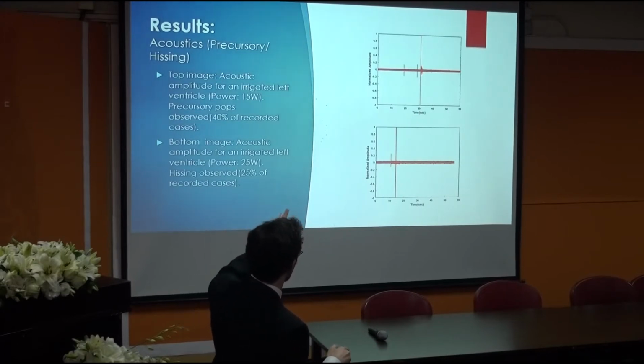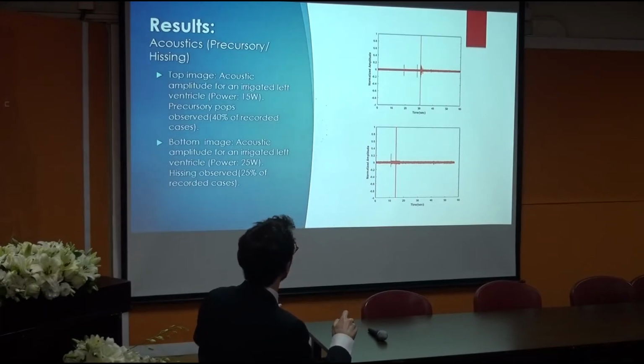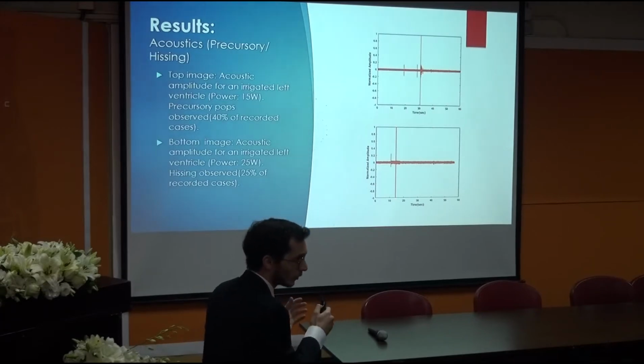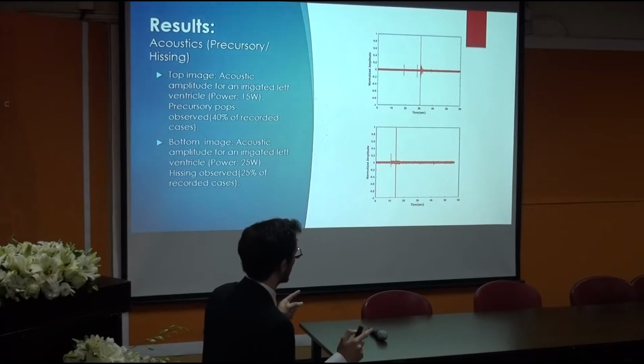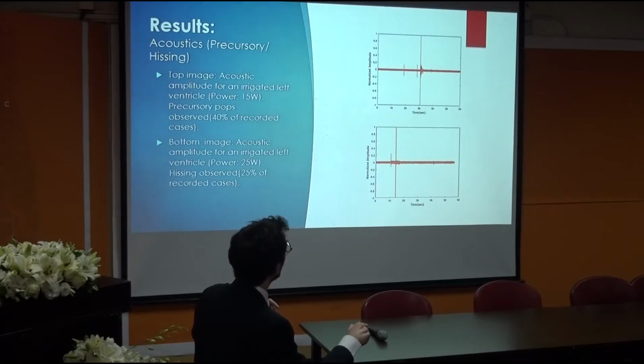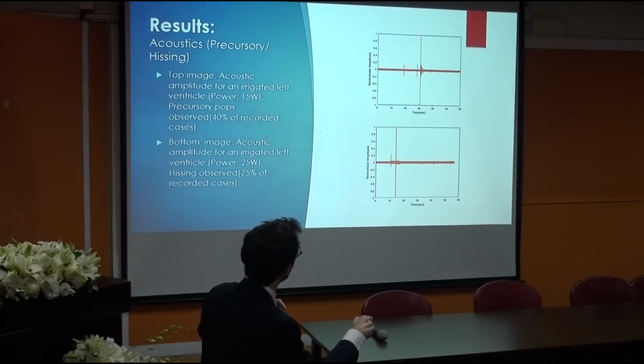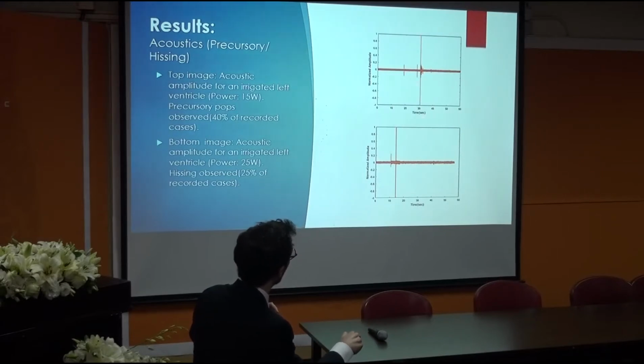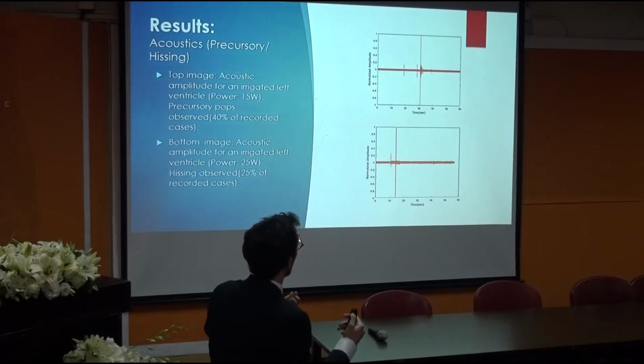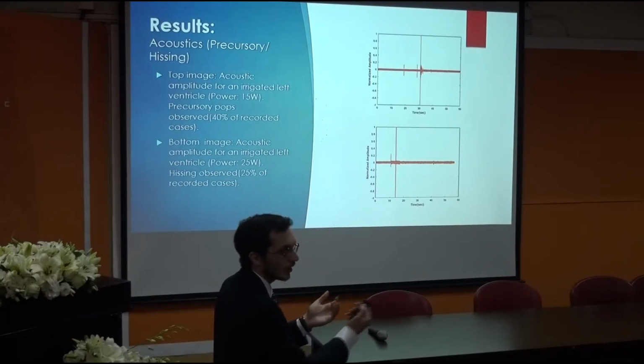I will explain it first: the precursory bubble and listening. We used a microphone, or a hydrophone, which has a longer time scale, and we were able to detect precursory bubbles. This is the main cavitation, the big detrimental one. You can see the intensity is much higher. And those are two precursory bubbles, called precursory because they start to happen before the big one. They're like a warning phase.